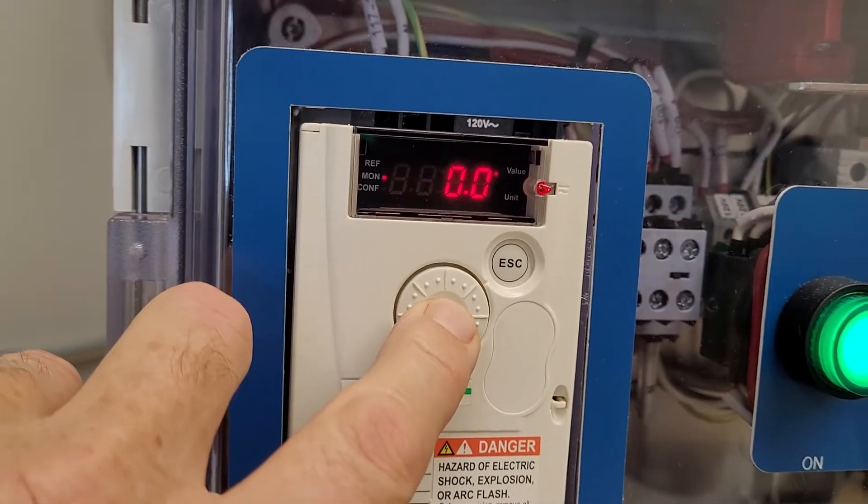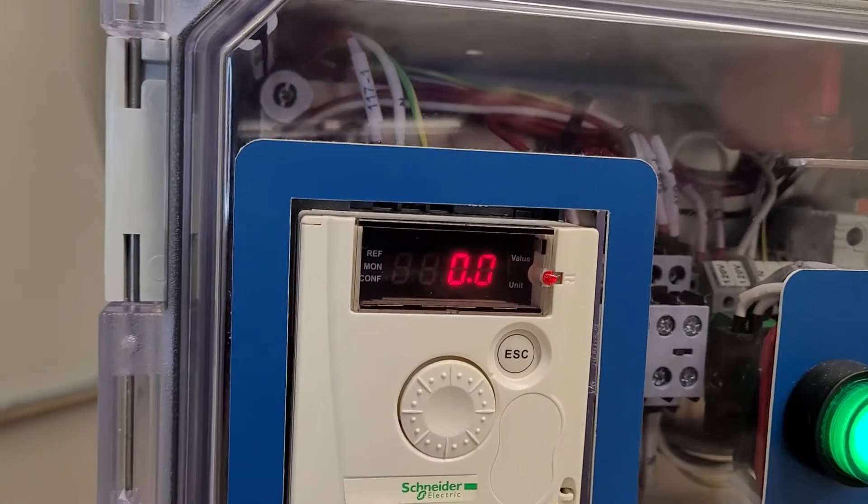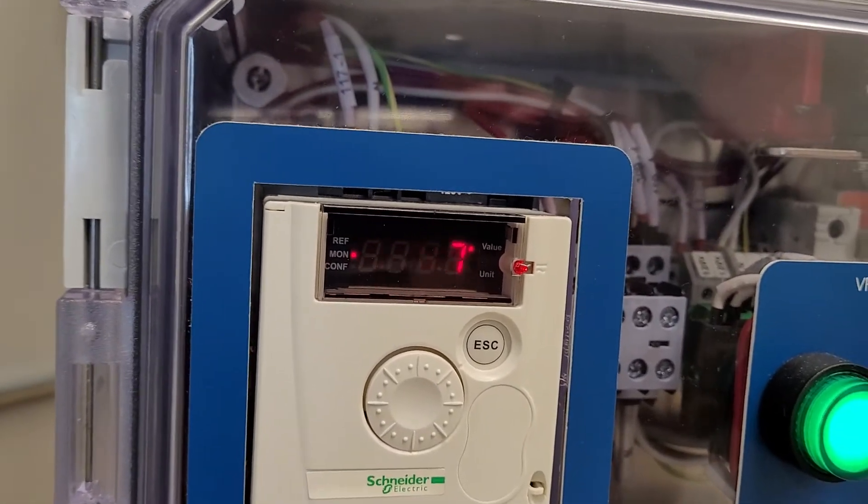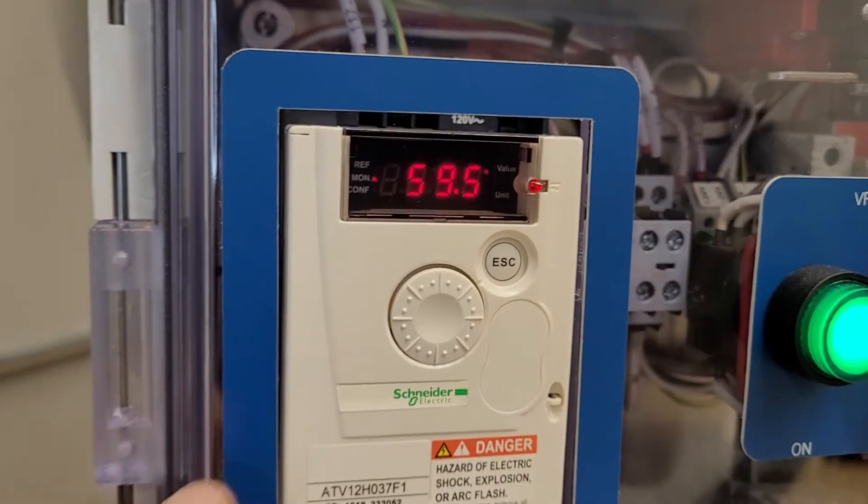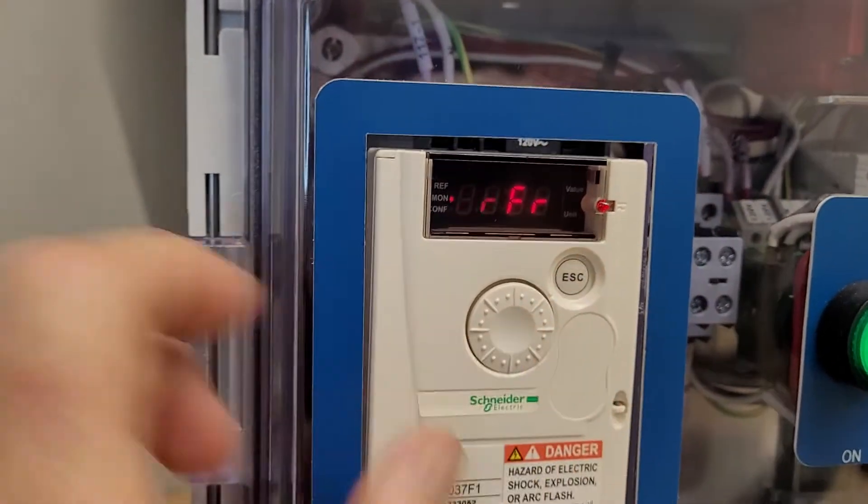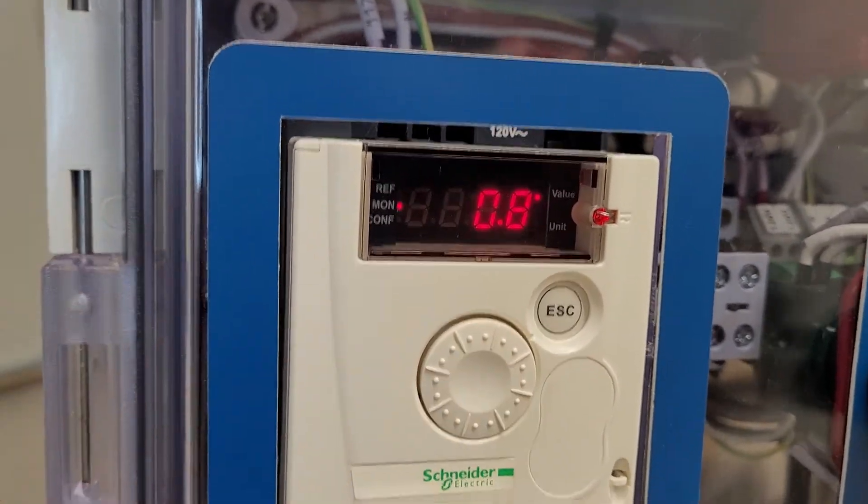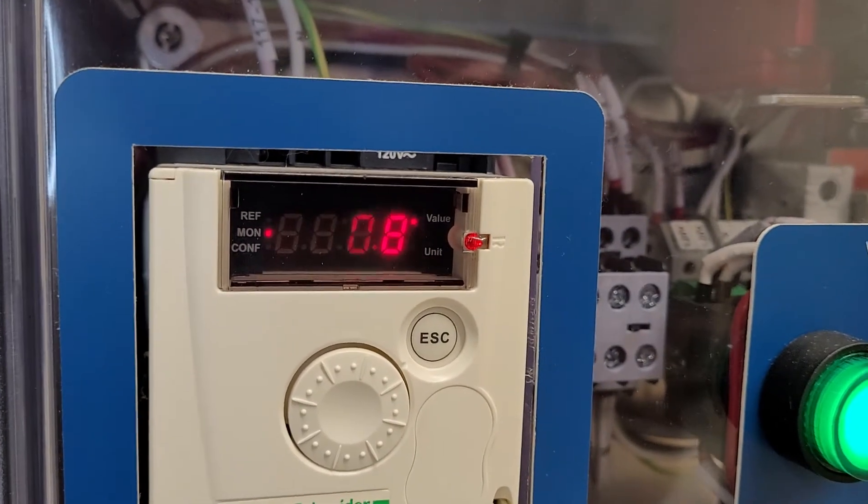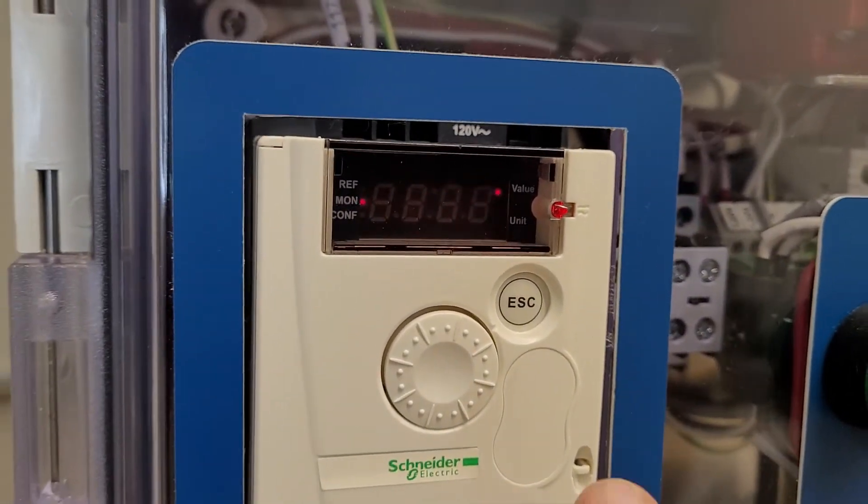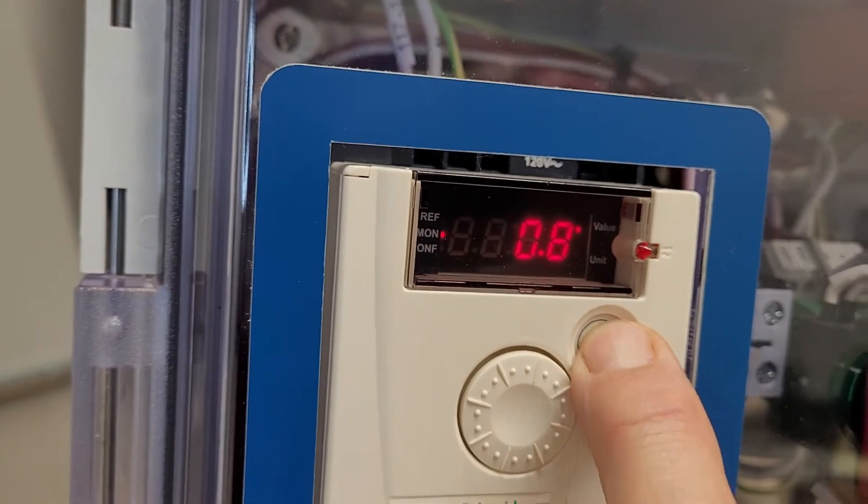The first one is the reference speed of the motor right now, or the output speed. I am going to start it running and you will see that change. We will just set that around 60 hertz. I will hit escape. And then the next one down is the motor current, which is very useful. You can determine what is going on in the field if the motor is loaded around 0.8 amps. That is pretty standard for a 1/3 horsepower that is not loaded.